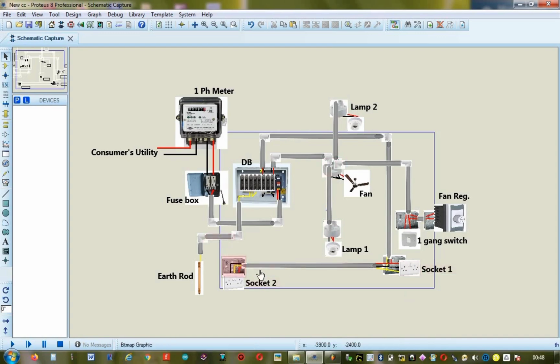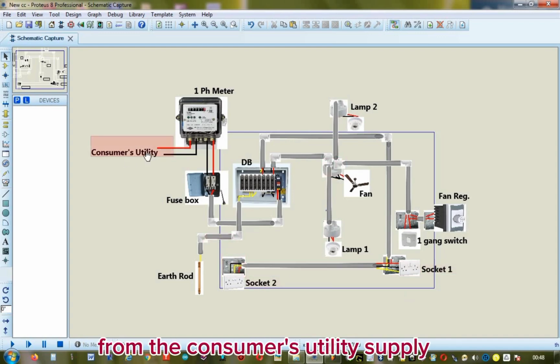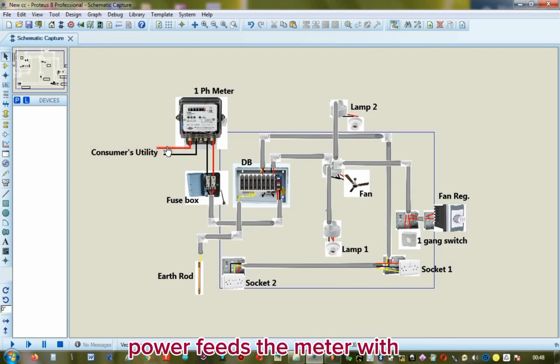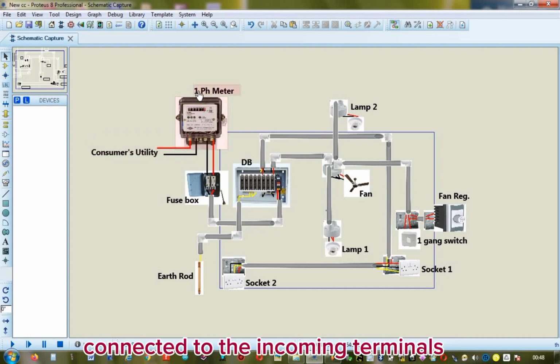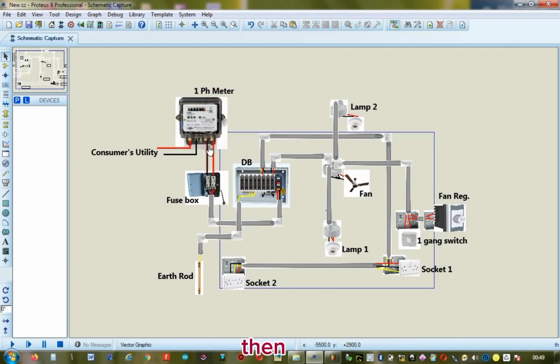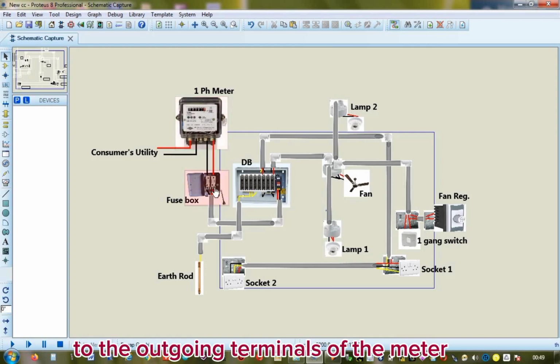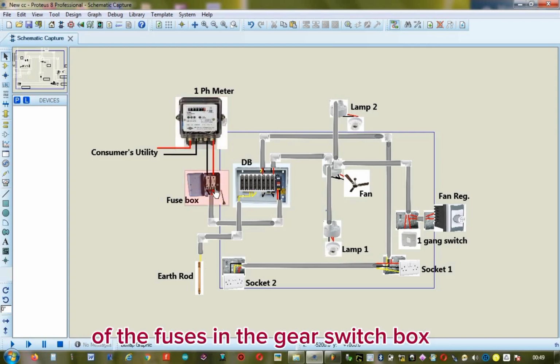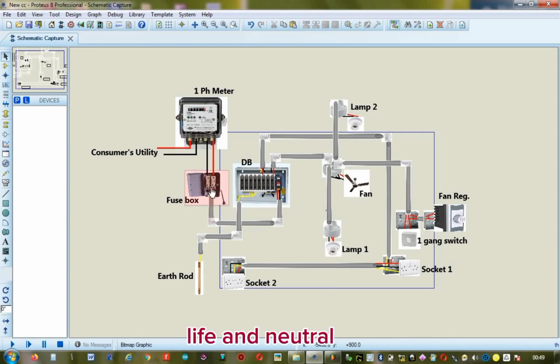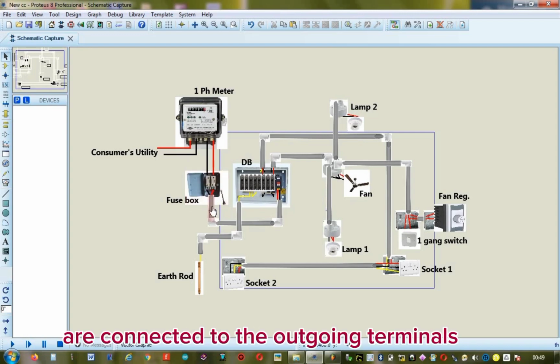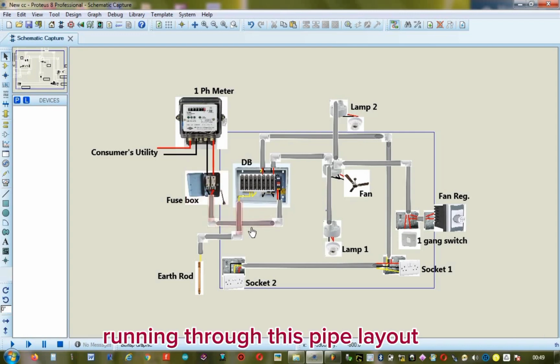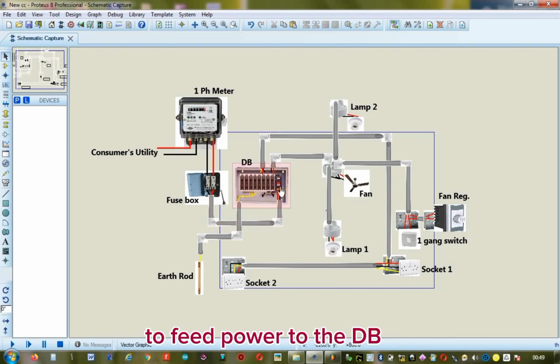outlet sockets. From the consumer's utility supply, power feeds the meter with 16 mm cables, live and neutral, connected to the incoming terminals of the one-phase meter. Then, using 10 mm wires, the live and neutral are connected to the outgoing terminals of the meter, linking to the incoming terminals of the fuses in the gear switch box. The same wire sizes, live and neutral, are connected to the outgoing terminals of the gear switch box, running through this pipe layout to feed power to the DB.